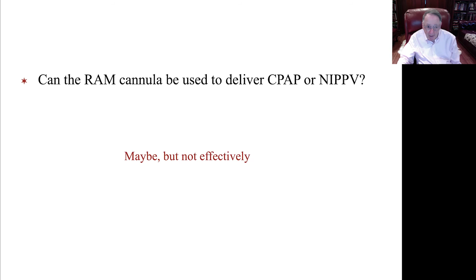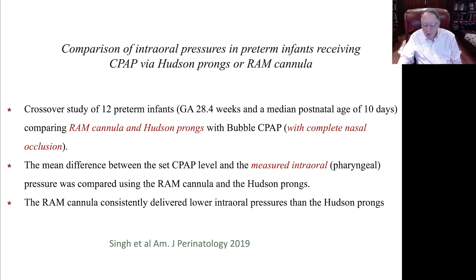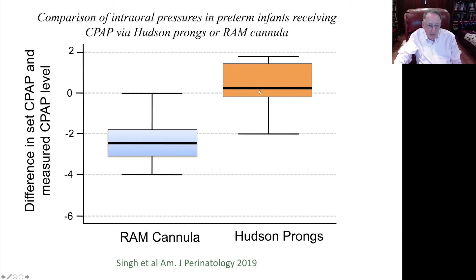So can the RAM cannula be used effectively to deliver CPAP or NIPPV? My answer, which I wrote to myself, is maybe, but not effectively. This was an in vivo study on preterm babies of about 28 weeks gestation, where they looked at the intraoral pressure delivered by the RAM cannula and Hudson prongs and compared it to the set pressure being delivered by the CPAP devices. The bottom line is the RAM cannula consistently delivered lower intraoral pressures than the Hudson prongs. Here is the difference between set CPAP pressure and the measured intraoral pressure. Here's the RAM cannula, and here's the Hudson prongs. The pressure was significantly lower with the RAM cannula.